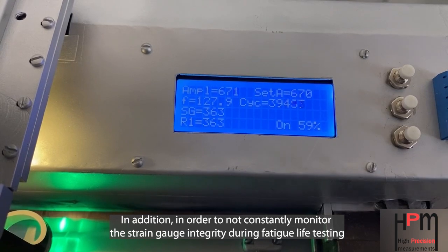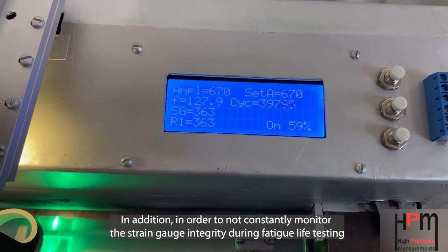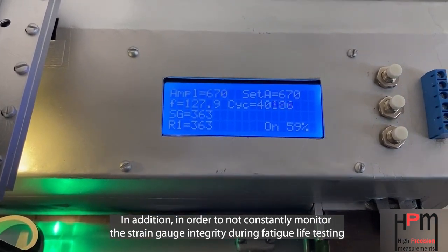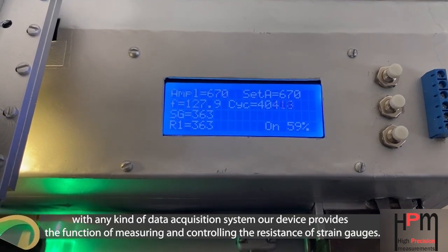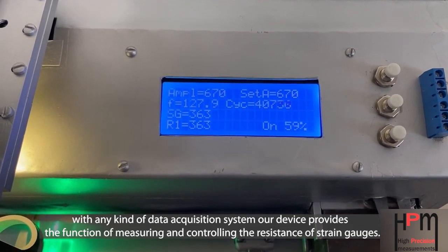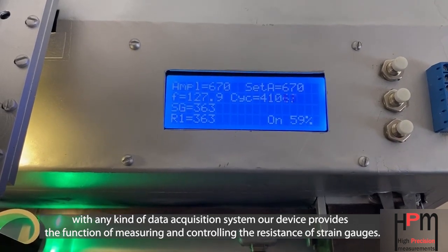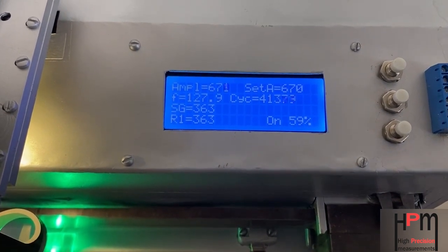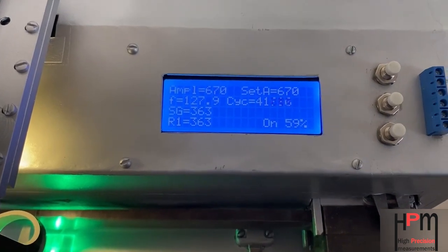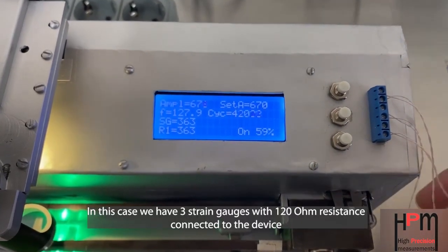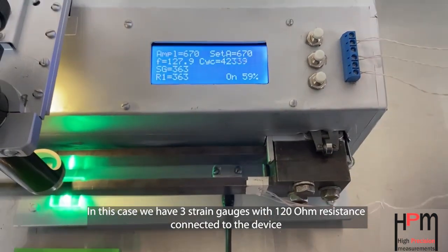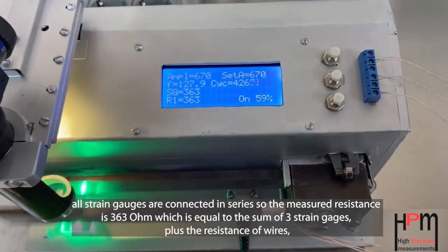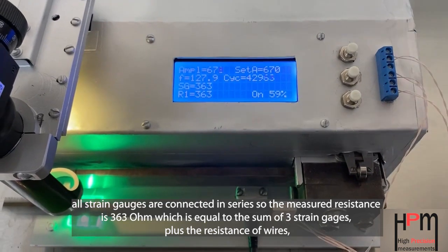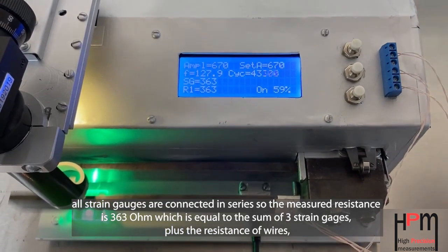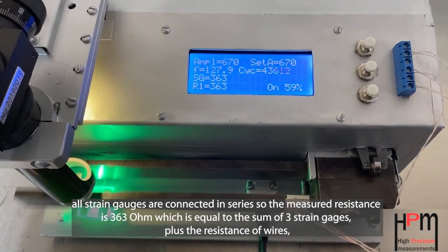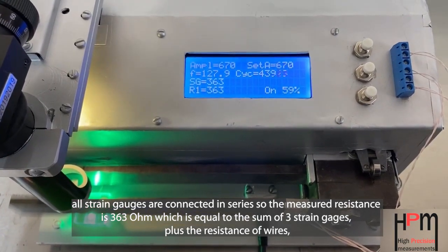In addition, in order to not constantly monitor the strain gauge integrity during fatigue life testing with any kind of data acquisition system, our device provides the function of measuring and controlling the resistance of strain gauges. In this case, we have 3 strain gauges with 120 ohm resistance connected to the device. All strain gauges are connected in series, so the measured resistance is 363 ohm, which is equal to the sum of 3 strain gauges plus the resistance of wires.